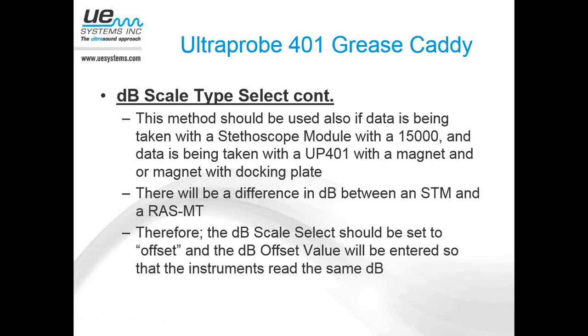There again, if you've taken those readings with the 9,000, the 10,000, or the 15, using the stethoscope module, you're going to get different decibel level readings with the magnet. So there again you would need to change your dB scale type to offset and then just set the offset value to whatever the difference is between the two instruments and modules.